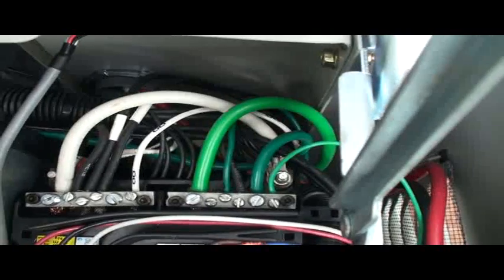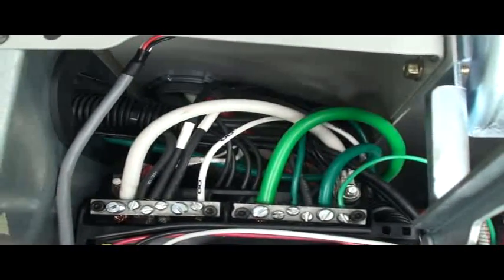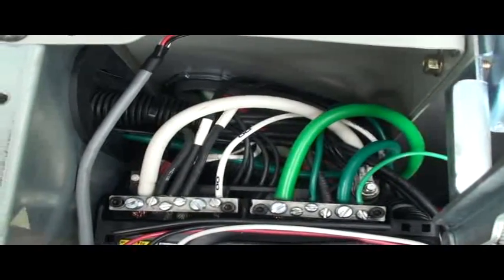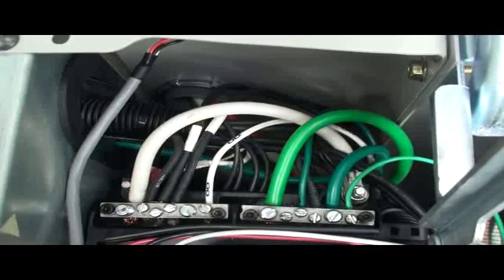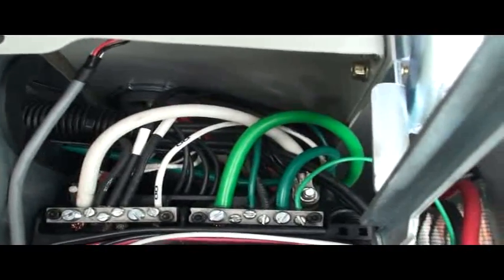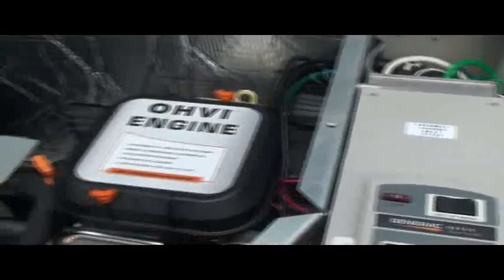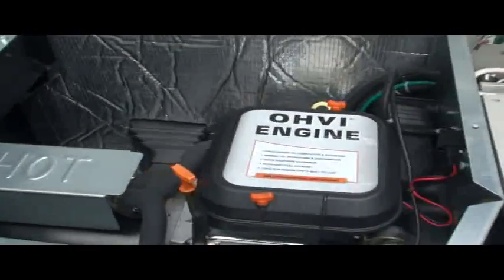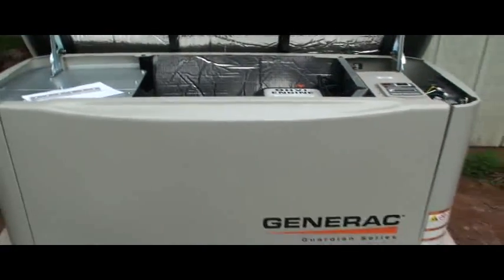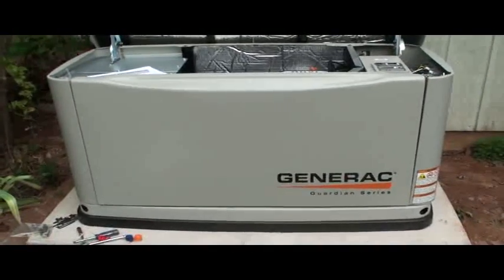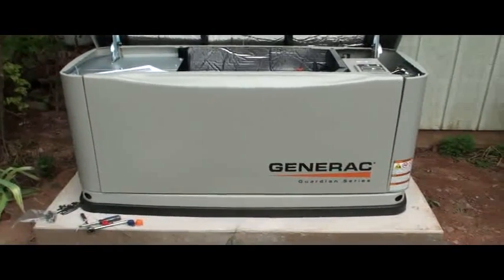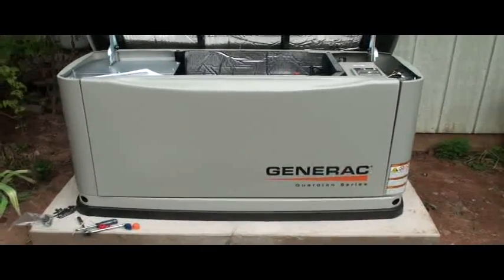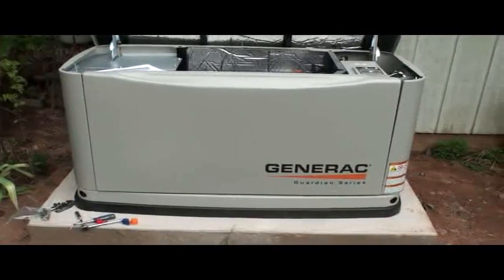And you can see those studs that are way down in there, pretty far. Kind of far to get down in to try and lug that to, so I kind of feel that this is a much better solution. So we had our generator running a little while ago, and it load tested well, and now I'll just finish up putting everything back together, and we should be ready for the next power outage. So this is how I solved the problem for me, for my Generac 6053.